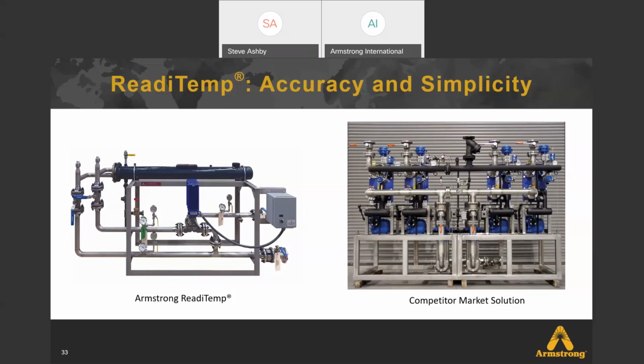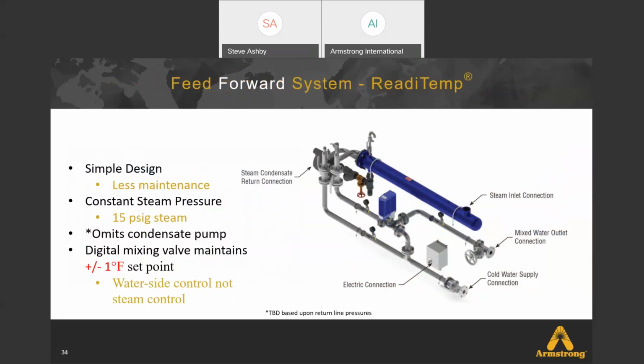By that, we mean we control the temperature on the outlet side of the heat exchanger by mixing overheated water with cold water. This will give you a little better idea of what we're doing here with this feed forward system. It's a very simple design, less maintenance. All we require is 15-pound constant steam pressure to feed the shell. This omits, in many instances, the need for a condensate pump. With 15-pound pressure, we can lift condensate 30 feet. So not in all instances, but in most of them, we can omit the condensate pump.